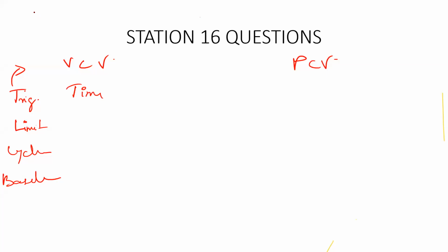If you set a rate of 12 per minute, which means every 5 seconds the ventilator has to breathe. Yes or no? Yes. So the ventilator is going quiet. Okay, 5 seconds is up, they've set 12 per minute, I'll start breathing. Then again, 5 seconds is over, I'll start triggering. So this time is the trigger for the ventilator in volume control breathing.